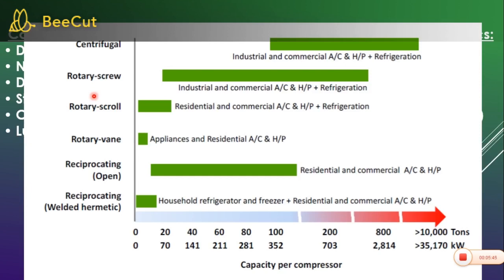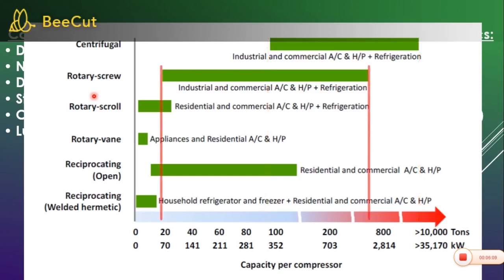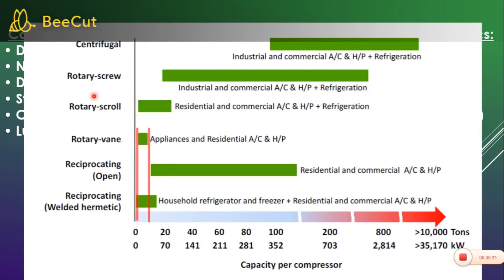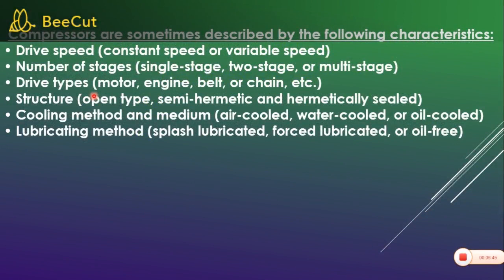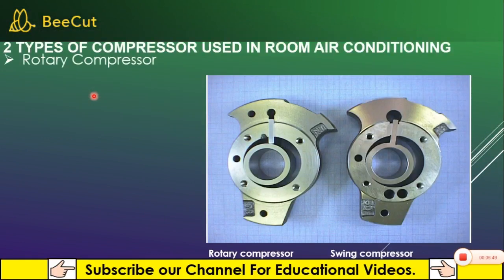This chart shows the capacity range for each compressor type. Centrifugal compressors handle the highest capacity. Rotary screw type handles high capacity — less than 800 tons, from start to 800 tons. Rotary scroll is used in residential applications and in VRF or VRV systems. Rotary vane type is used in room AC and window AC for residential use, and the rotary compressor is used in refrigerators.